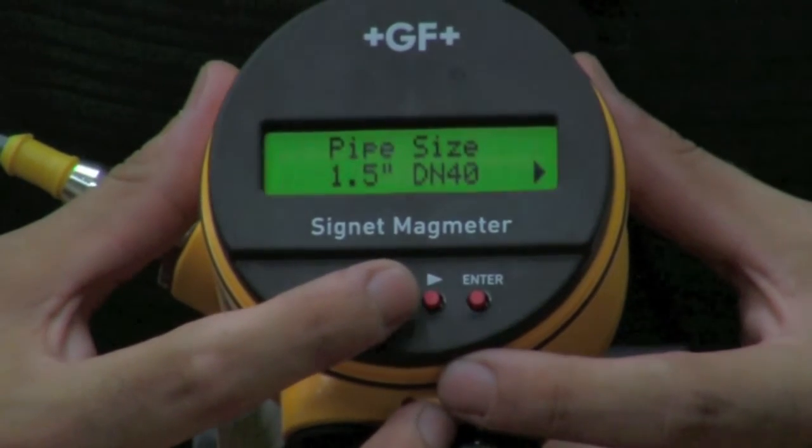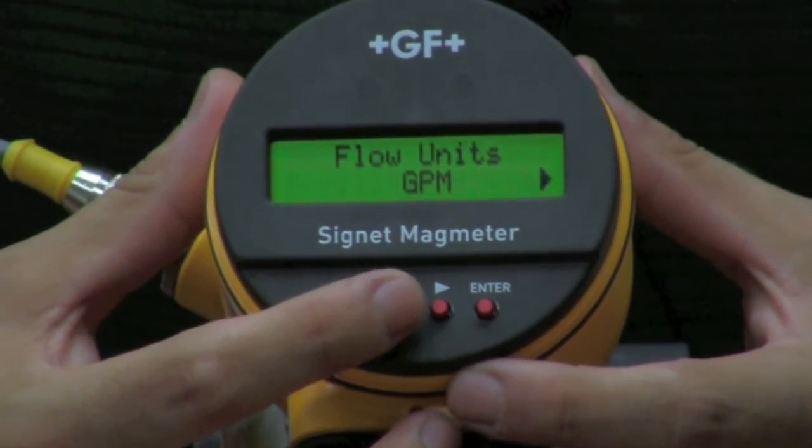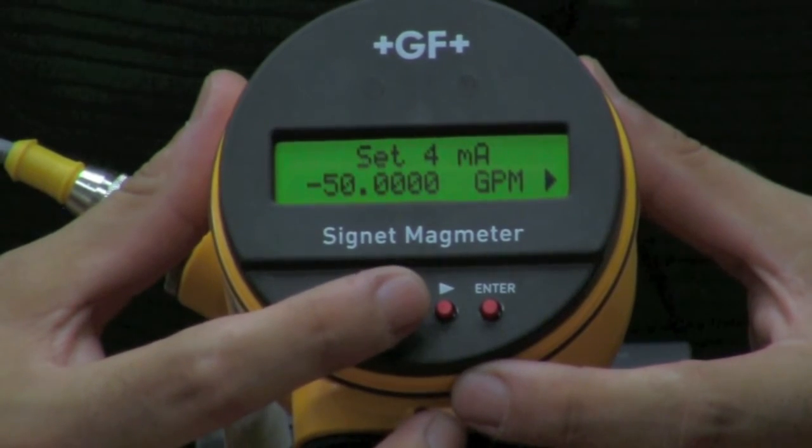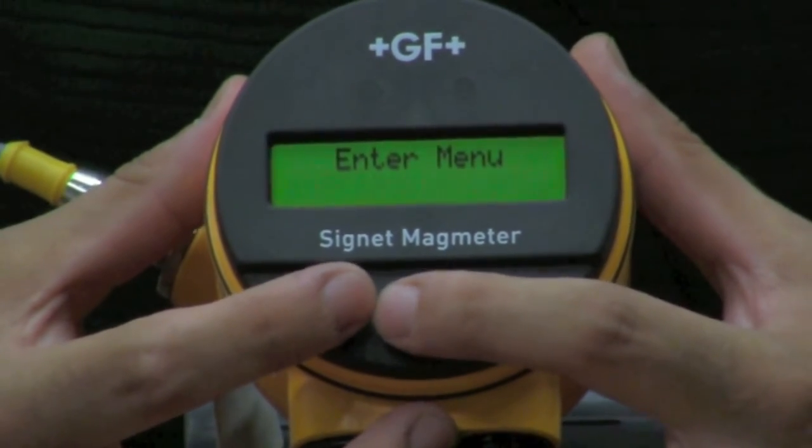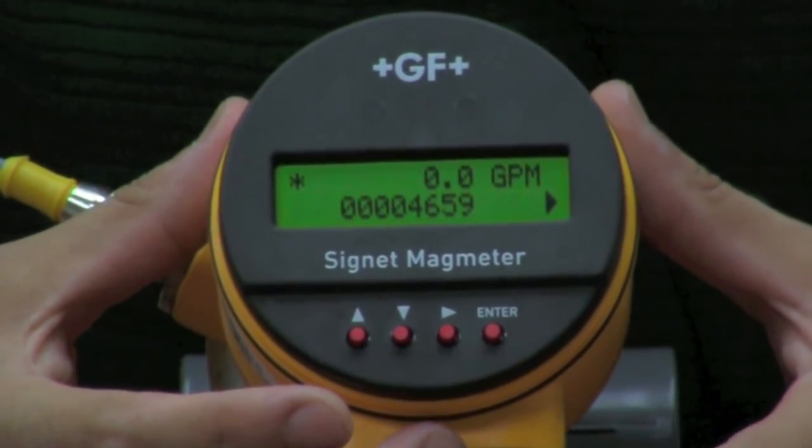The K factor, the line size, the units, and then we can scale our 4 to 20. From here we press our down and up twice to back out, and we are now able to read flow.